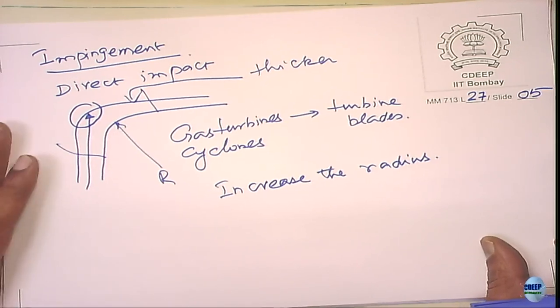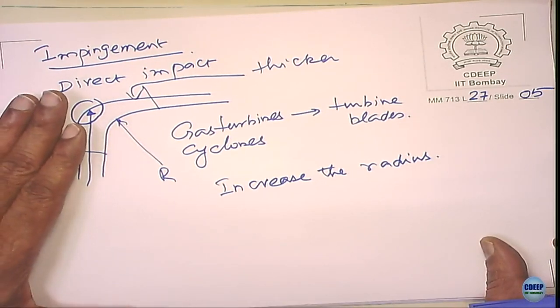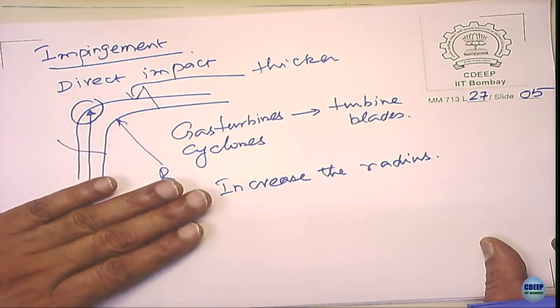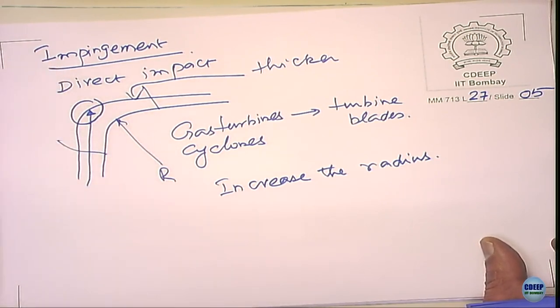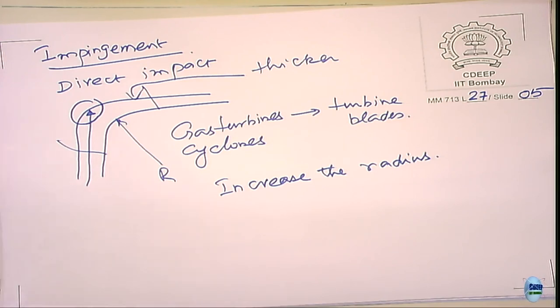So when you look at this, it becomes clear that design plays a very important role in minimizing erosion corrosion. Anything that reduces the impact of impingement, anything that reduces turbulence, can increase the erosion corrosion resistance of the system. So it is a design parameter as much as a material parameter, as well as the environmental conditions operating in a given system.